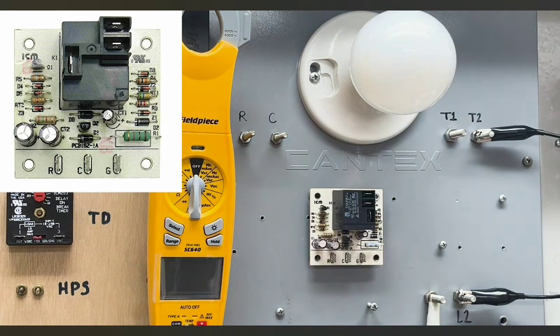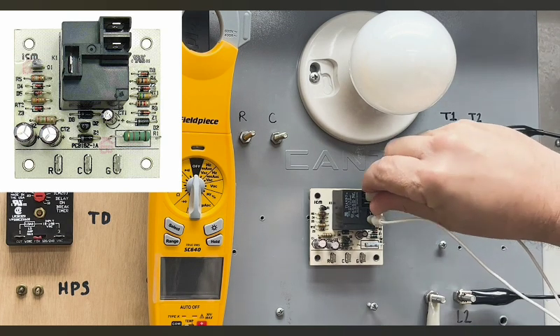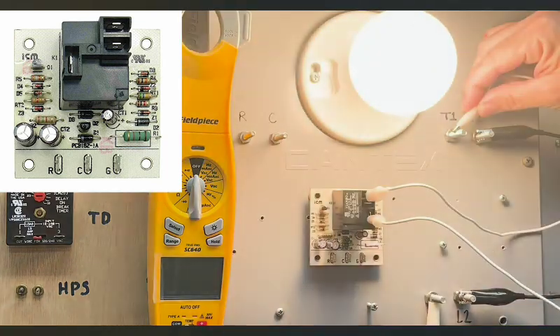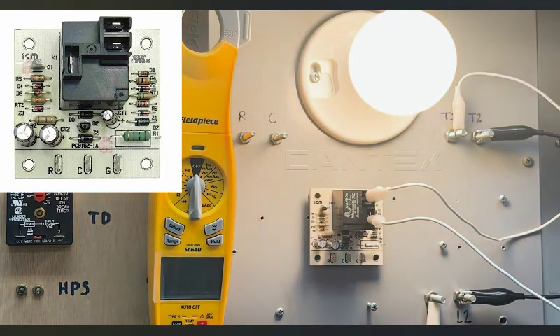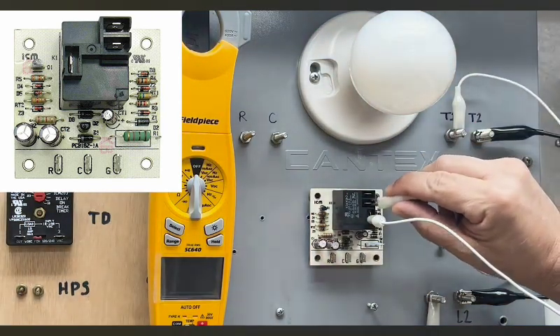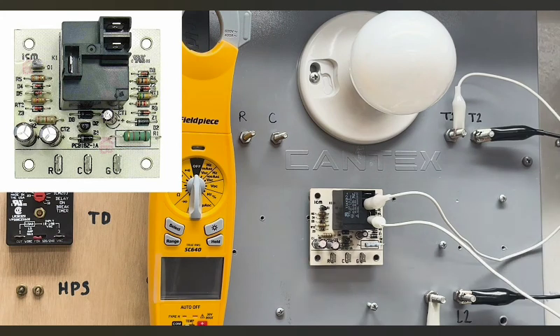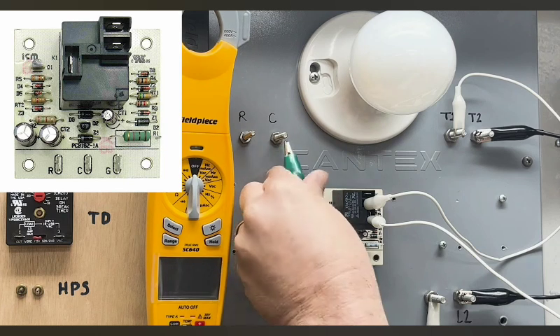So what we're going to do now is take L1 and energize our common terminal on the relay portion of the control board. We're going to come out of that with our normally closed, just to show you that there's always power there no matter what. I'm just going to touch T1. And so as you see here, if we were to leave it there, the load is always energized. If we were to come down and wire it to its traditional terminal, which will be the normally open, that's open now, so there's no power there. So our load has L2 present all the way through, but it's lacking L1 because we're breaking L1 across the relay. We're going to go ahead and energize the board with common and R, 24 volts.